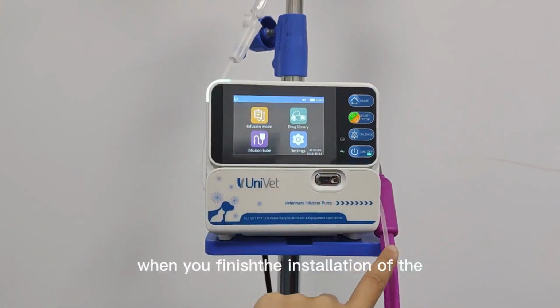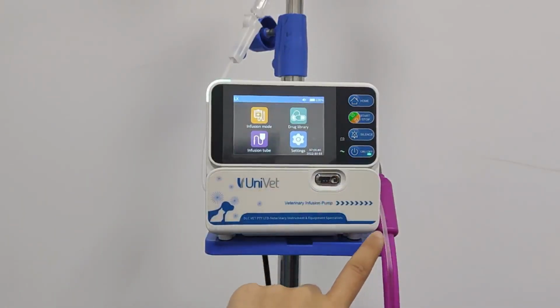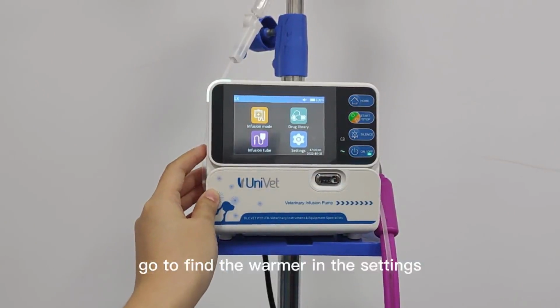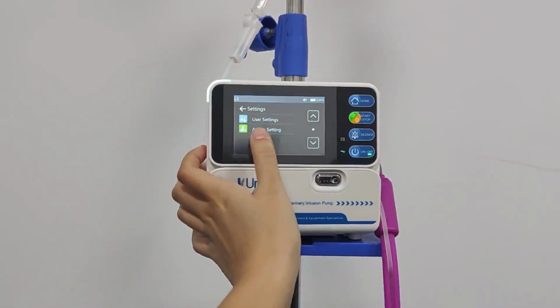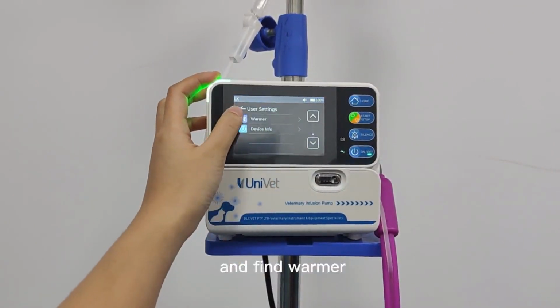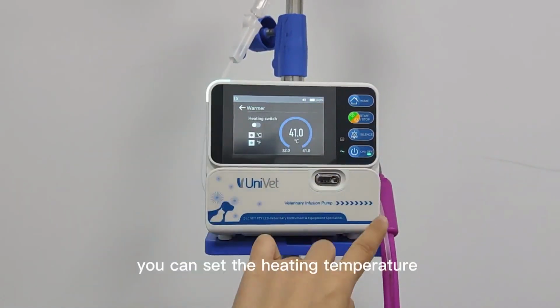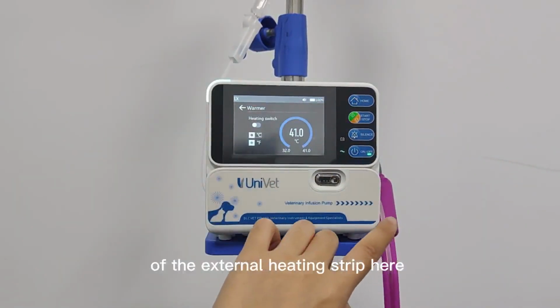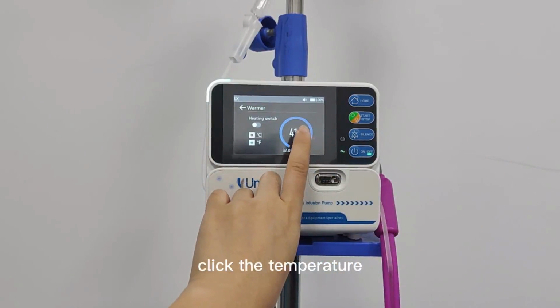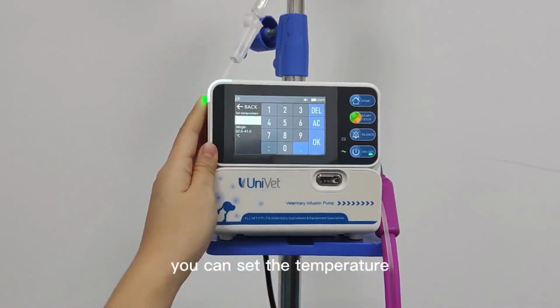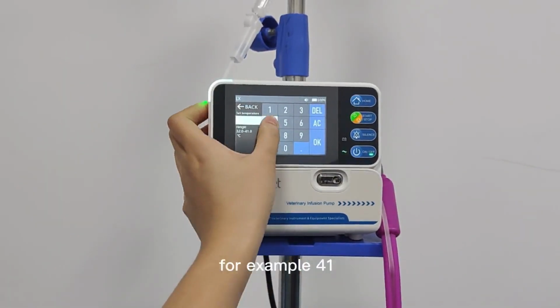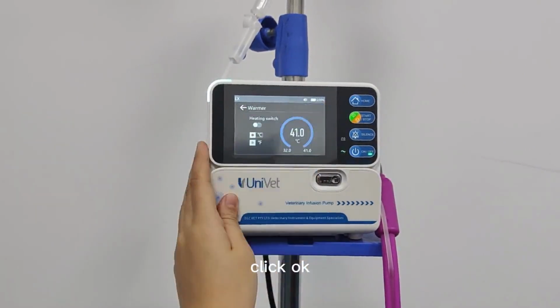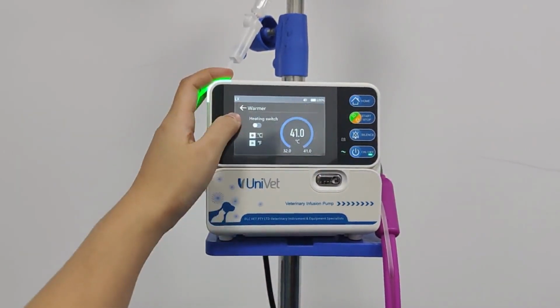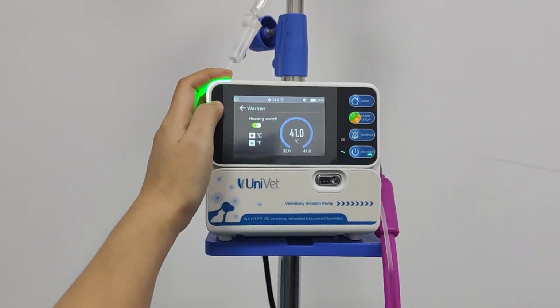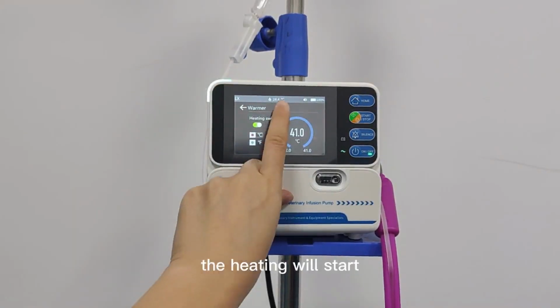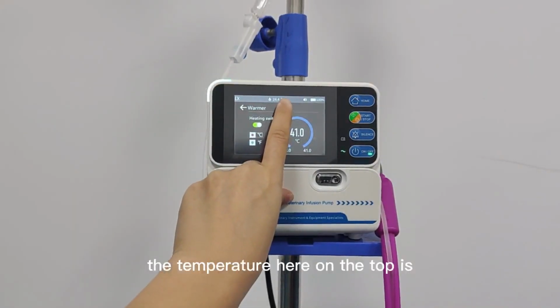When you finish the installation of the external heating strip, go to Warmer in the Settings. Settings, User Settings, and find Warmer. Click Warmer. You can set the heating temperature of the external heating strip here. Click the temperature. You can set the temperature, for example, 41. Click OK. When you turn on the heating switch, the heating will start. The temperature here on the top is the real-time temperature.